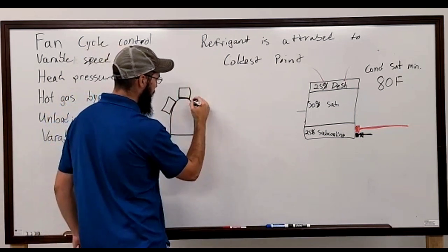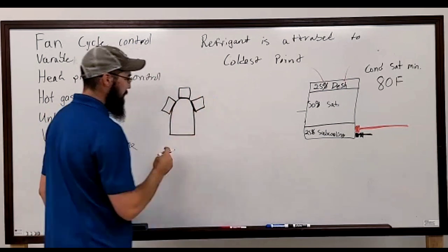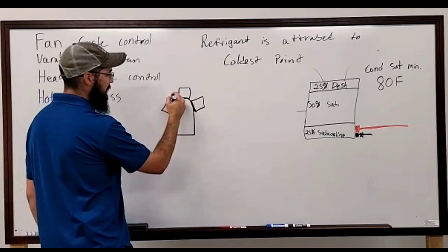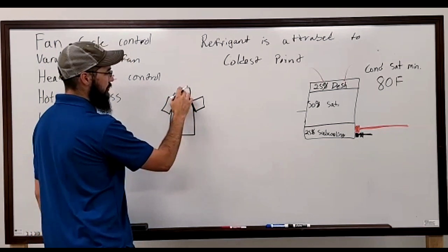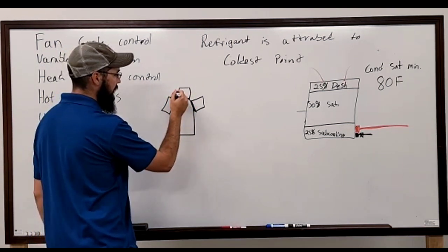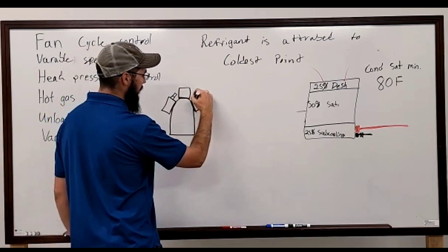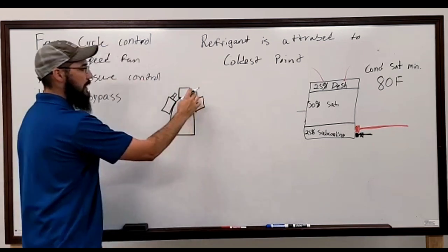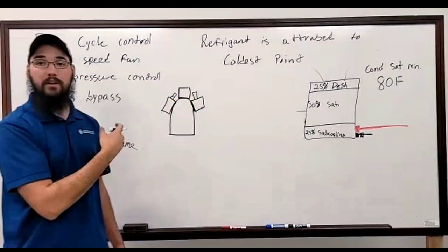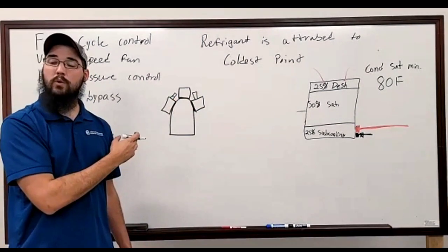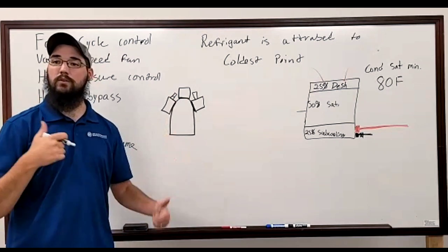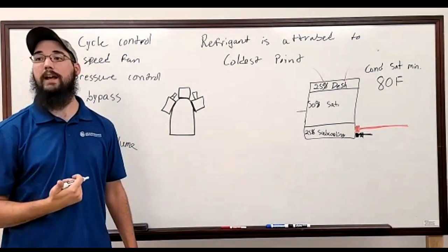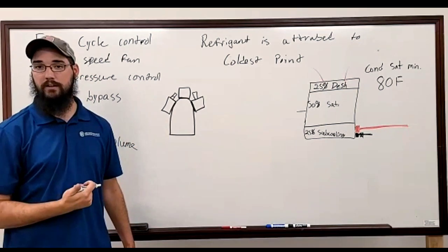You'll have three heads, our beautiful artwork. And each of these heads will have, typically the discharge head, the top head won't. But this head will. And you can on this one too. You'll have an unloader. Now, whether that unloader has a solenoid coil or has a big brass nut on it will decide whether it's electromechanical or whether it is straight mechanical, pressure actuated.